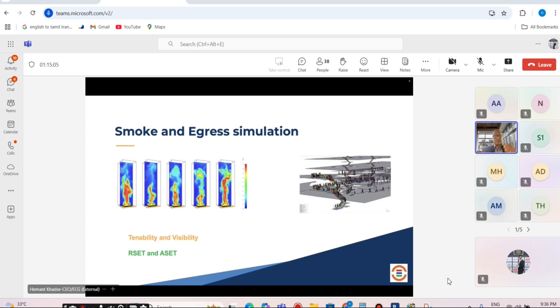Tenability is something expected from best practice at 1.8 meters to 2.5 meters based on the height of the building or occupancy type. The visibility, again, could be between 4 meters and 20 meters, depending on the building where you expect visibility to be ensured. Visibility need not be a hazard, but it can become a hazard or it can delay your evacuation. Tenability also might delay, but if smoke is going to be inhaled in a very large proportion, it is definitely going to hinder or become a hazard to human life safety.